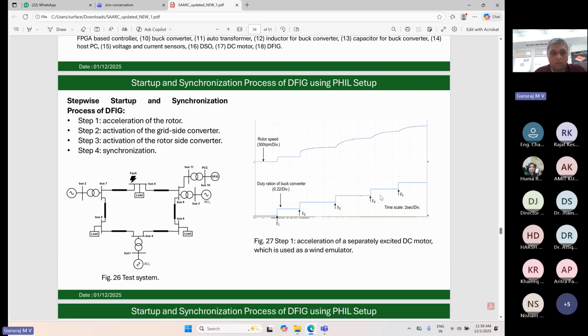So just some of the results to show you how the startup and synchronization process takes place. Step number 1 is the acceleration of the rotor, then the activation of the grid side converter so that you can maintain the DC link voltage constant. Once you have the DC link voltage constant, why do we need to accelerate the rotor? First of all, because the converters are low rated. So we are generating the voltage at the stator side by giving voltage from the rotor side.